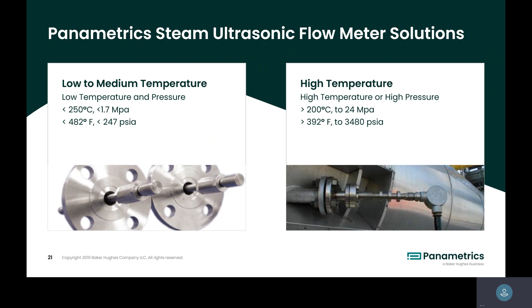You have the transducer, probably the most common one here, with this normal temperature crystal on the side, titanium construction because it's really durable overall. The handles are designed based on the pressures and temperatures.